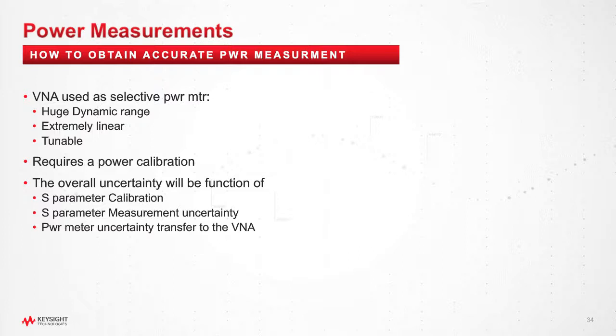The beauty of using a VNA for power is that this is an example of how we can get the power at a device reference plane. We want the power at the device plane, but in reality we cannot put a power meter there, because the power meter can be put at the coaxial interface, but not inside. So these three plots show P out at the measurement plane without the correction, and P out at the device plane. Because by using a VNA, you can de-embed in the proper way anything between your measurement plane and your device plane. This is another feature that you cannot get with a power meter.